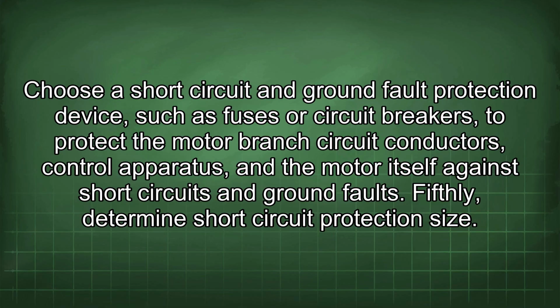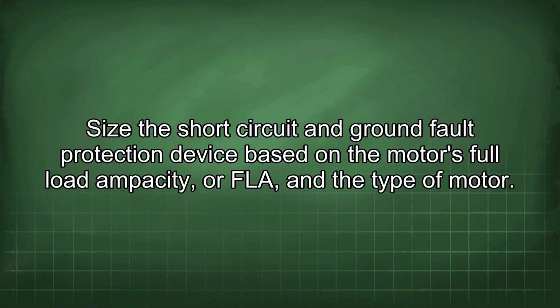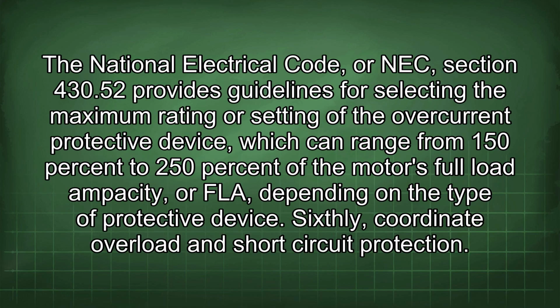Fifthly, determine short circuit protection size. Size the short circuit and ground fault protection device based on the motor's full load ampacity, or FLA, and the type of motor. The National Electrical Code, or NEC, Section 430.52 provides guidelines for selecting the maximum rating or setting of the overcurrent protective device, which can range from 150% to 250% of the motor's full load ampacity, or FLA, depending on the type of protective device. Sixthly, coordinate overload and short circuit protection.